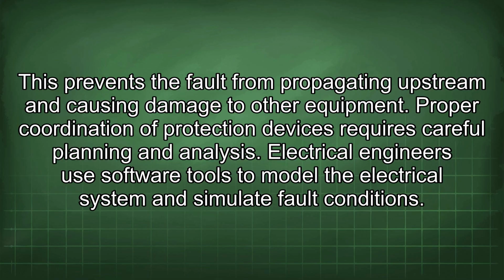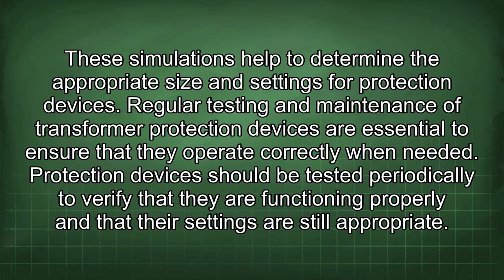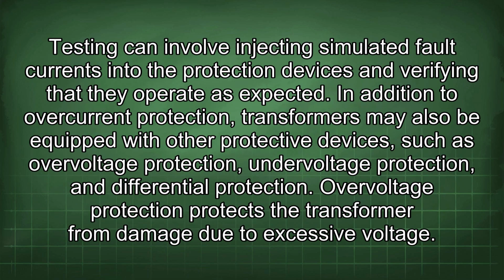Proper coordination of protection devices requires careful planning and analysis. Electrical engineers use software tools to model the electrical system and simulate fault conditions. These simulations help to determine the appropriate size and settings for protection devices. Regular testing and maintenance of transformer protection devices are essential to ensure that they operate correctly when needed. Protection devices should be tested periodically to verify that they are functioning properly and that their settings are still appropriate. Testing can involve injecting simulated fault currents into the protection devices and verifying that they operate as expected.